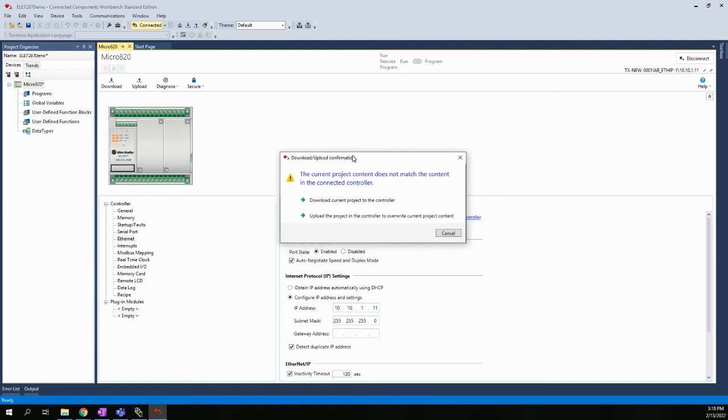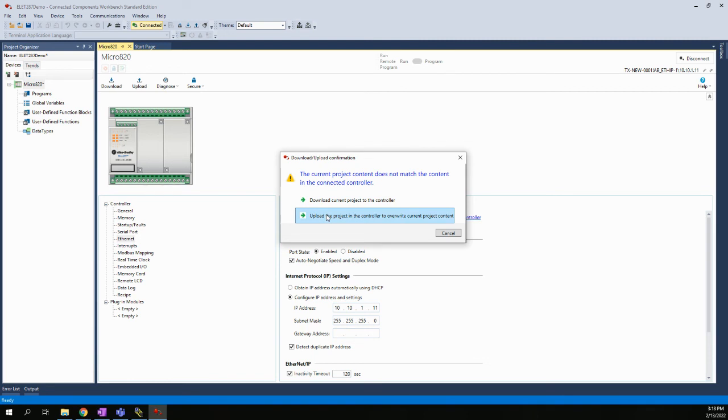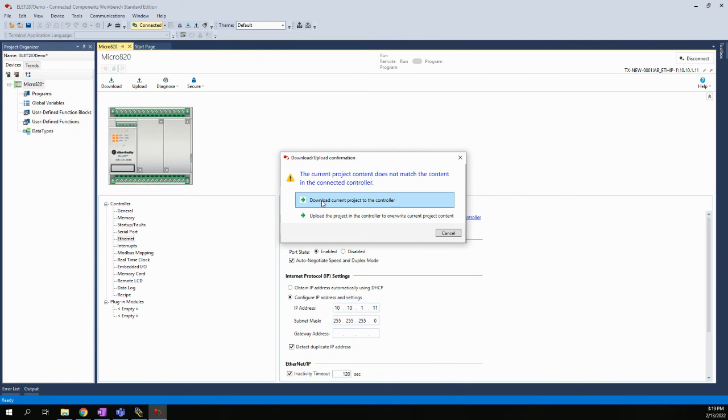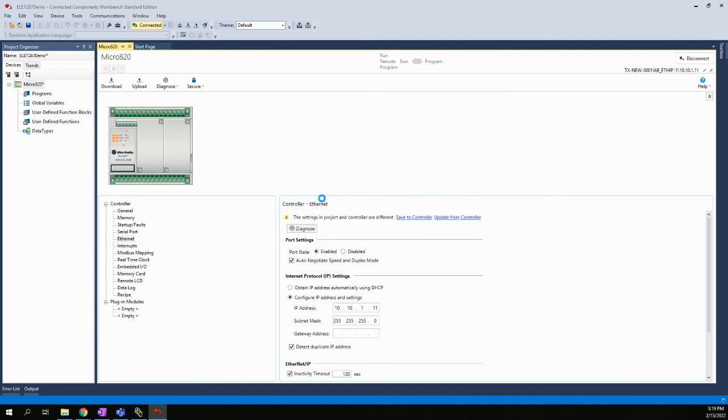Now when I did that, my connection path changed. It now shows this is just the name of my computer and the AB ETH-IP-1 and then the IP address itself. Now, this will come up to the current project does not match the contents in the connected controller. They're just basically telling you that the project you've created is different than what's inside of the controller. Do you want to download or do you want to upload? Very important to note. If you want to download, that means I'm going to take what's on my laptop computer and download it to the Micro820. So I'm going to overwrite whatever is in the Micro820 PLC. If I were to choose upload, it's the exact opposite. It'll take whatever is in the Micro820 PLC and upload it to my laptop and overwrite what is in my laptop. So be very careful there and make sure you choose the right thing. For the most part, we're going to only do downloads in this class. There could be a time where you want to upload out the controller because you don't know what's in there and you want to see what the program was that you had in there. But probably the majority of what we're going to do in this class will always be a download. So just make sure to choose that properly. Otherwise, you could overwrite some of your hard work and you'll have to do it again.